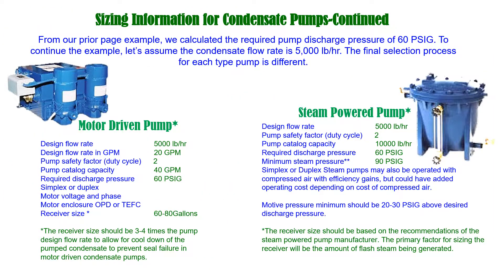Using the discharge pressure of 60 psig calculated, let's look at the selection of either a motor or steam powered pump based on 5,000 pounds per hour of condensate flow. An important conversion is 500 pounds per hour of steam becomes 500 pounds per hour of condensate, which is equal to 1 gallon per minute of flow. In both cases, sizing the receiver is critical to ensure proper pump operation.